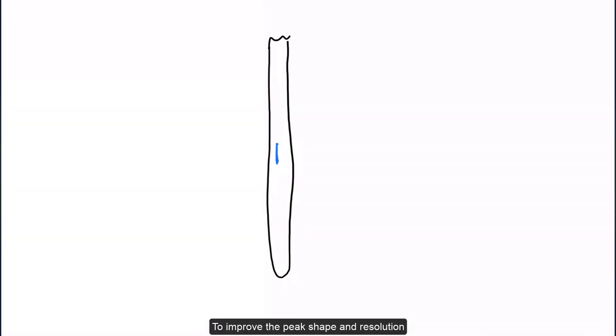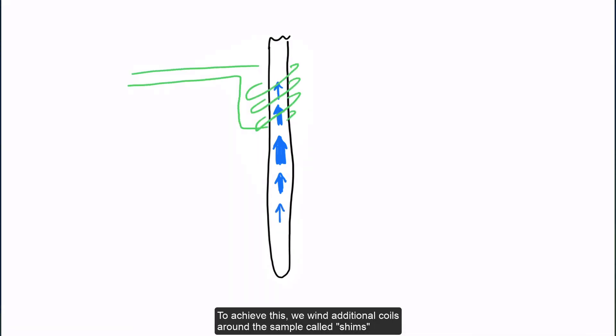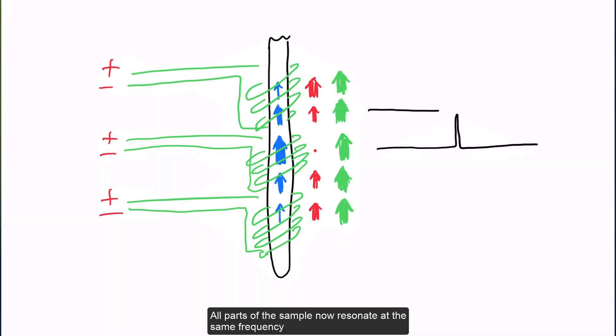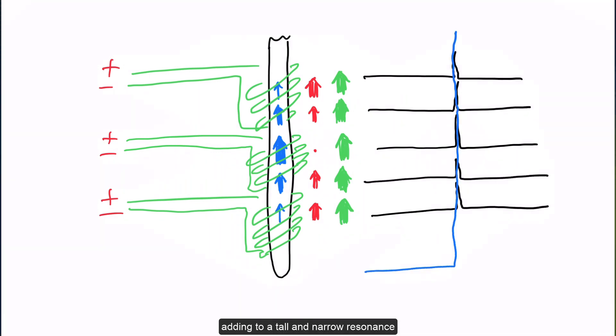To improve the peak shape and resolution, we have to correct the magnetic field in different parts of the tube. To achieve this, we wind additional coils around the sample called shims. We can supply electric current to the shims to compensate for changes in the magnetic field and make the field uniform or homogeneous. All parts of the sample now resonate at the same frequency, adding to a tall and narrow resonance.